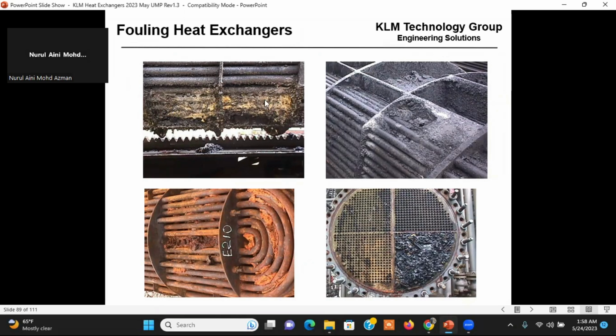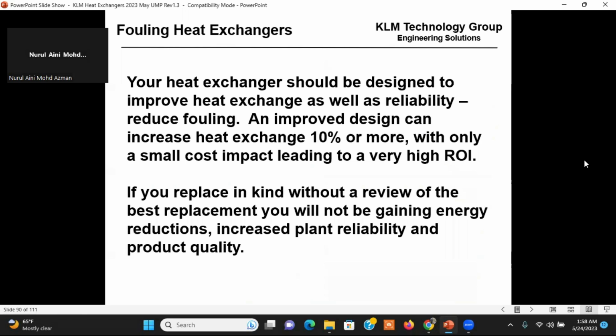All right, so this heat exchanger's lost probably 20–30% of its surface area. This one's probably lost 30% of its surface area. This one's lost a lot of surface area. Obviously, this cooling water flow is not what it's wanted to be. So here's kind of how you don't design heat exchangers. And we do this all the time. We design them poorly for fouling services. All right, so how do we design them? Okay.